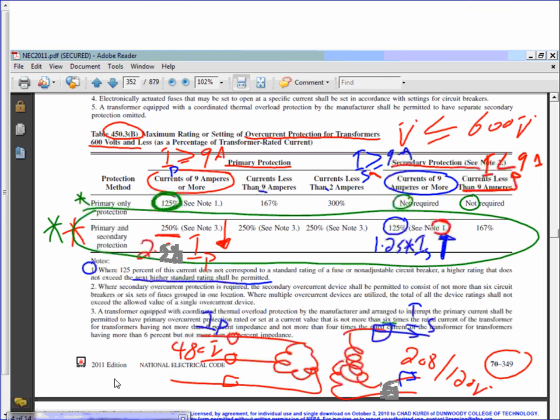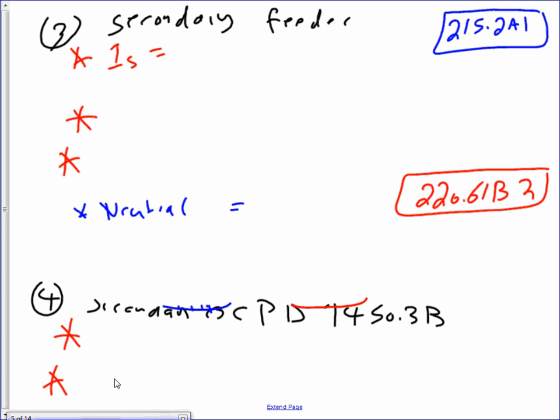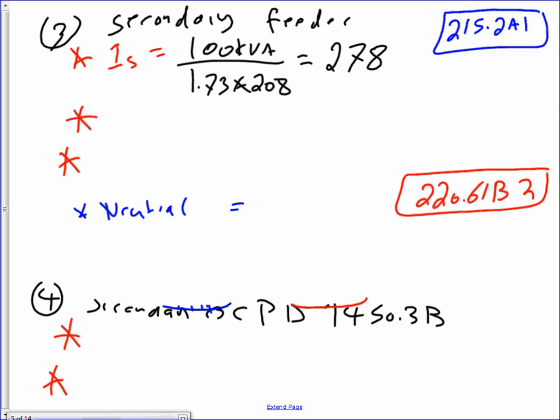Okay, so let's go to the secondary side. The secondary side, my friends, the same thing. You need to take 100 kVA, divide this by 1.73 times 208. Anybody knows why we divided by 208 instead of 480? Because the secondary side is 208. That will give you a healthy 278 amp, 278 amp.